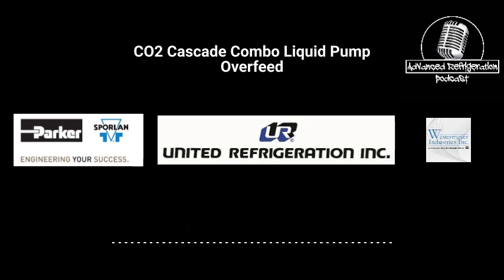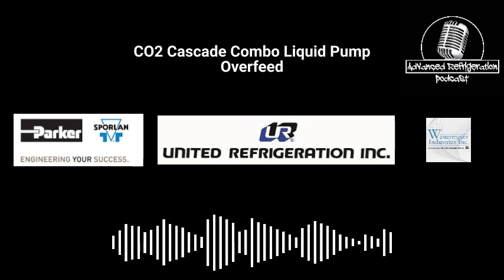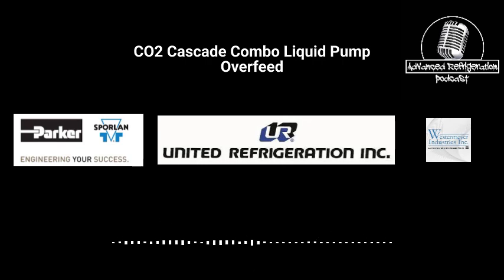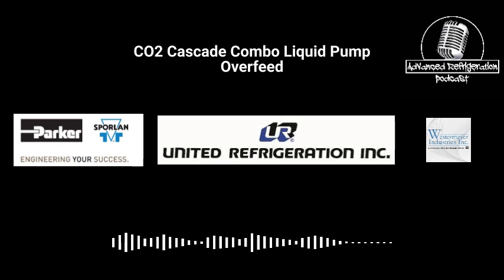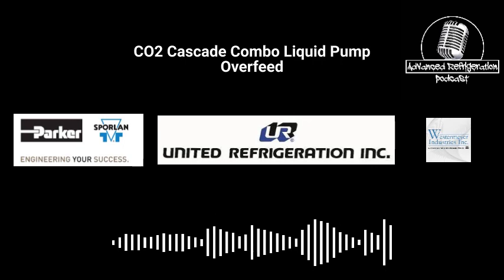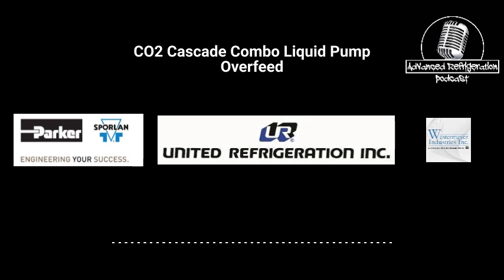I get it. I've never seen it yet. I would think it would be less prevalent on the medium temp ones, but I wonder if they have the same icing issues where you get that oily, frosty junk in the heat exchanger, and then it causes that pressure drop. I wouldn't think so. You are running 20 degrees, but it's still below freezing. I guess it'd be more prevalent in the ones running like negative 26 degrees saturated. Yeah, regular liquid pump overfeed. I wouldn't think they would have that problem on the medium temp side. I think that's more of a low temp one.